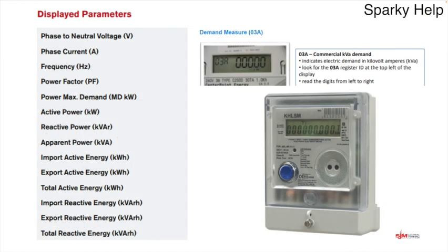We can take the guesswork out with new technology — specifically smart meters. Smart meters have been around for a long time for commercial installations. If you get a chance to look at one, press the button on the front and it will register things like maximum demand. Among the many values most meters measure, one particularly relevant here is power maximum demand — not maximum demand in KVA, but a recorded maximum demand over the lifetime of that meter. This would be far more accurate than the On-Site Guide estimate, and therefore a much better value to put on EIC certificates.